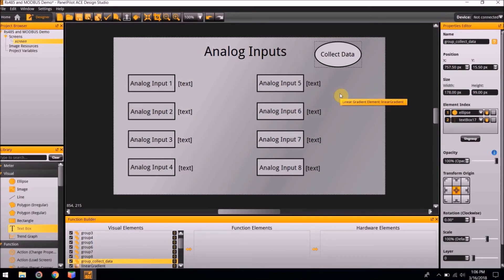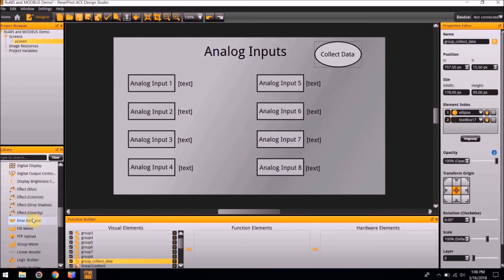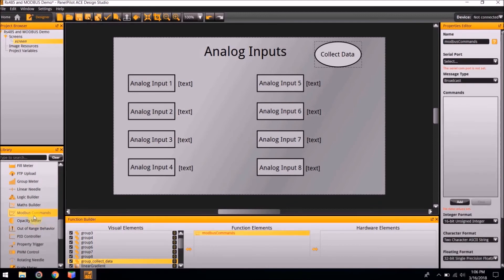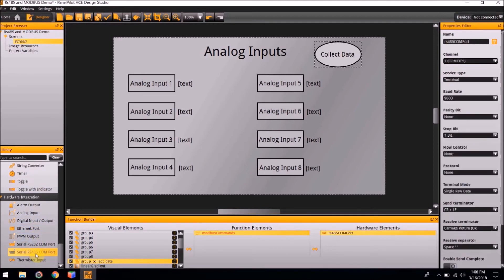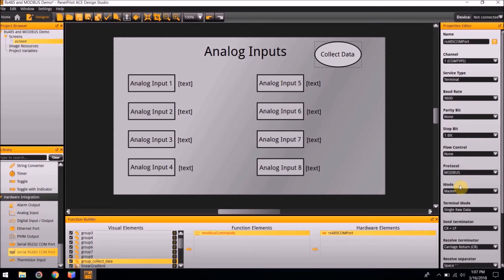Now all the visual elements are completed for this project. Next, we are going to move on to the function and hardware elements. First, we are going to add the Modbus Commands function element from the library — search for Modbus Commands and add it to the project. Next, we are going to add the serial RS-485 COM port hardware element. This hardware element will allow us to receive the information from the Neptronics board. In the RS-485 COM port hardware element Properties Editor, we are going to leave all the original settings except in the protocol section — we are going to change this to Modbus. This hardware element is complete.